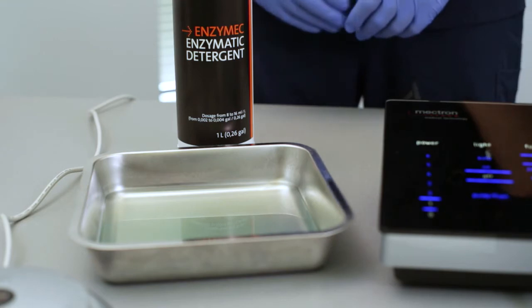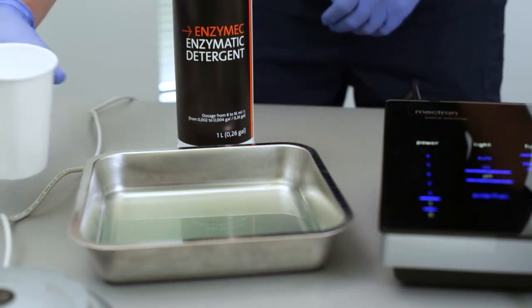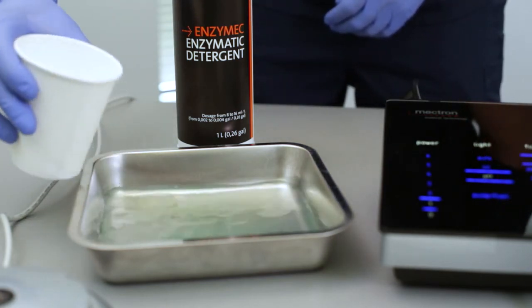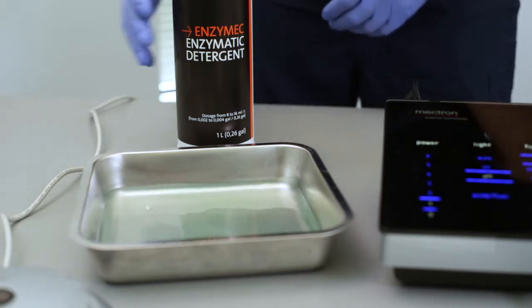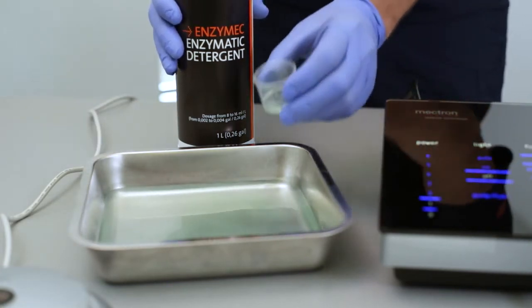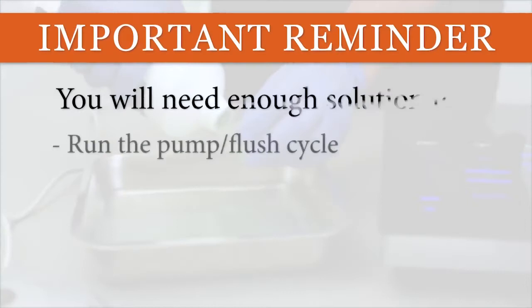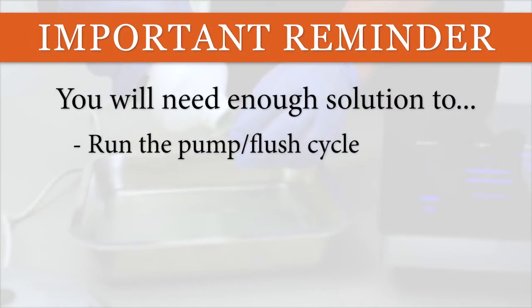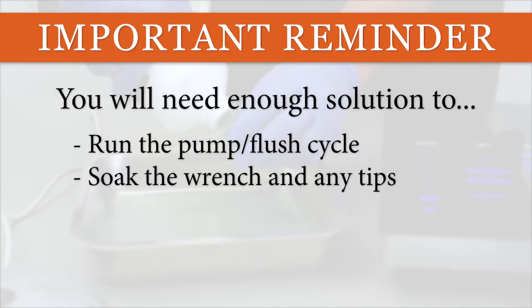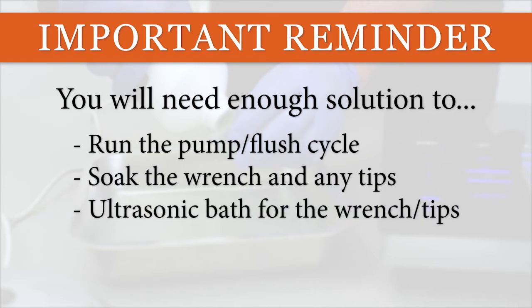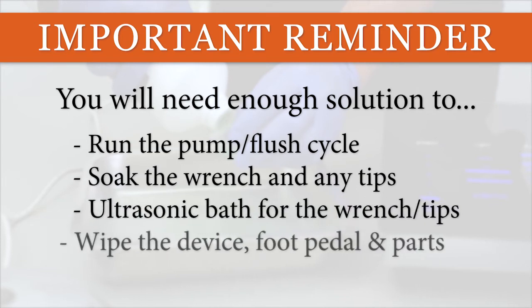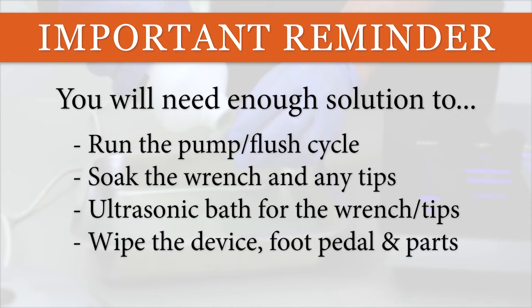If you are using Enzymec by Mectron as your enzymatic cleaner, dilute the detergent with water from a 1:8 to 1:16 ratio. You will need enough solution to separately run the pump flush cycle into the dish, for the initial soak of the wrench and any tips into the bowl, for the ultrasonic bath of the wrench and tips, and to wipe down the device, foot pedal, and all external parts.